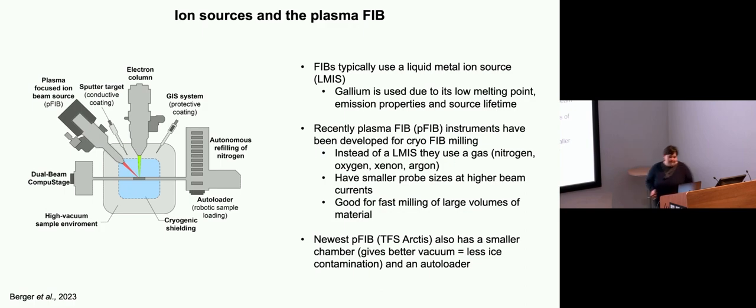You may have heard recently, there's been a lot of talk about plasma FIBs. The more typical source that we use, at least in the context of cryo milling, is a gallium source, a liquid metal ion source. You can use other metals, but normally for the milling is the gallium. But more recently, there have been these plasma instruments that use a gas source instead. These have advantages because they're very good for fast milling of large volumes of material.